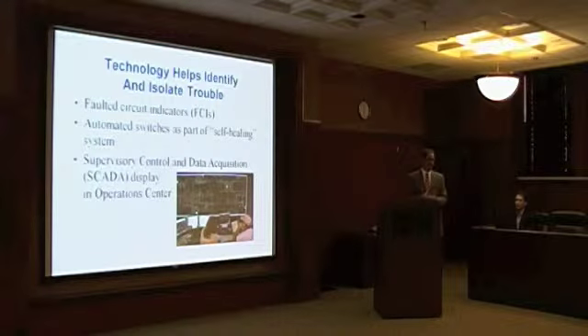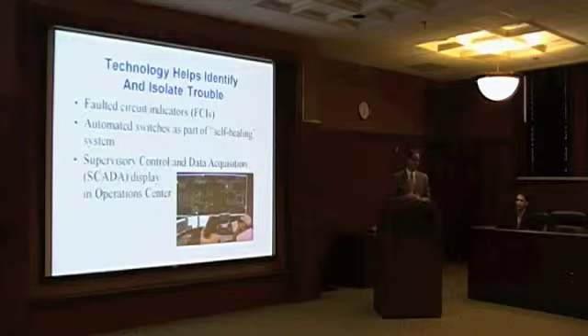I think you maybe asked about the customer meeting. The difference there is if it's a breaker that goes out in the substation through the SCADA, we do know about that. But as those lines go out and serve our customers, we have sections that line may peel off and serve this neighborhood or this little commercial part. And we protect our equipment with fuses or reclosers at each of those taps. So if something happens that doesn't affect the breaker, then we may not have visibility of that.